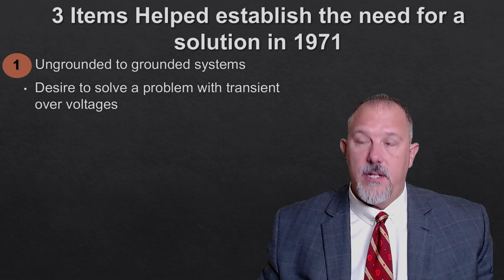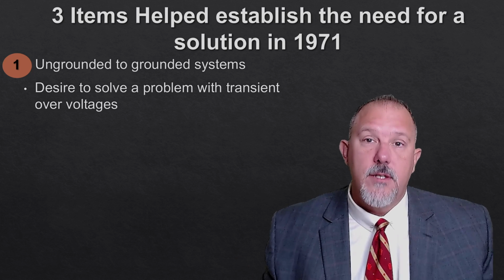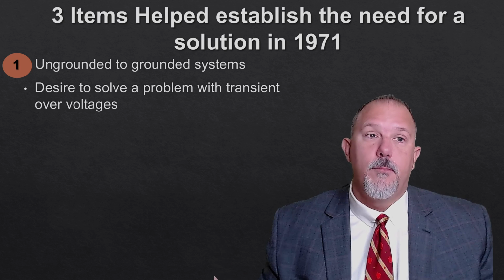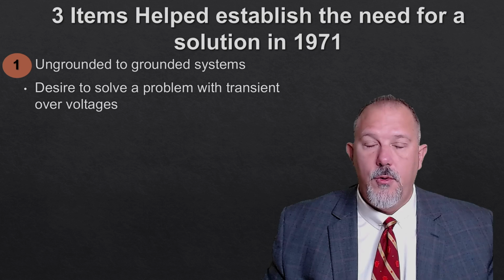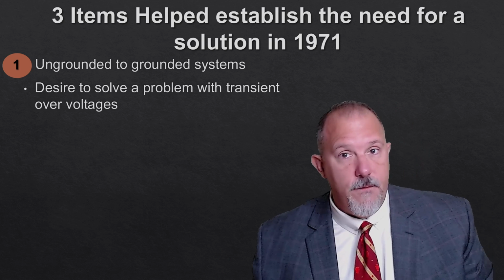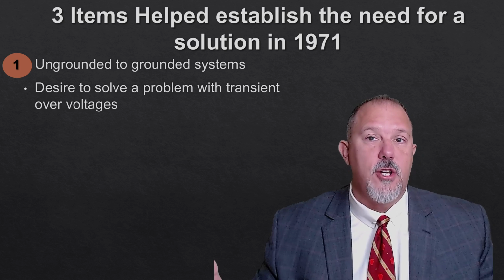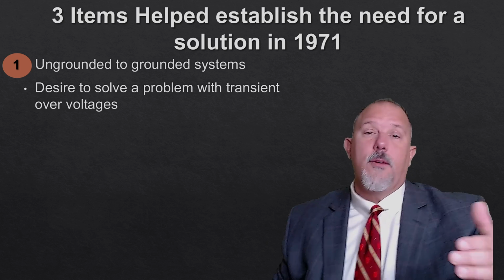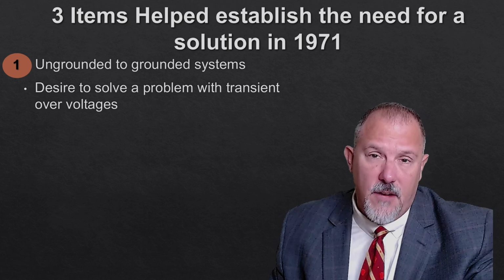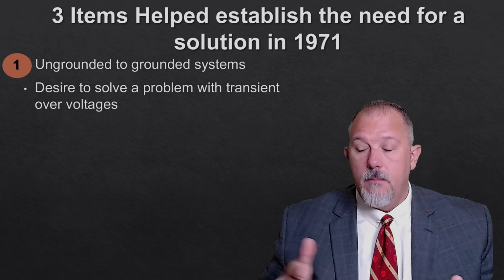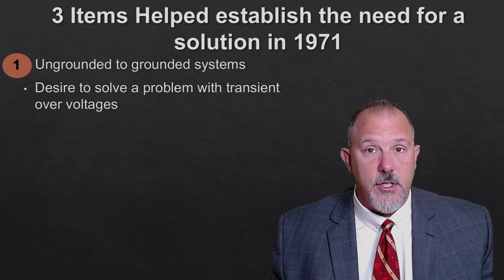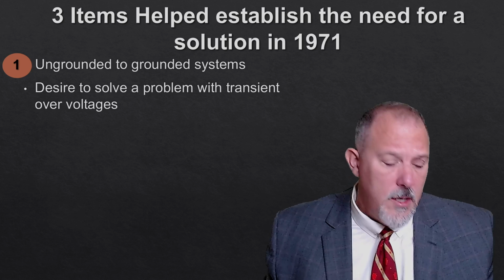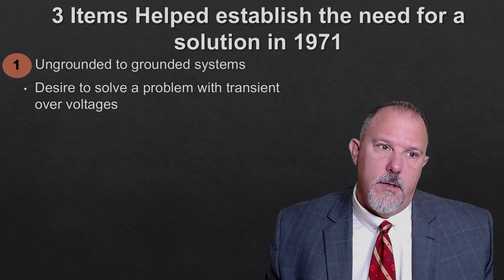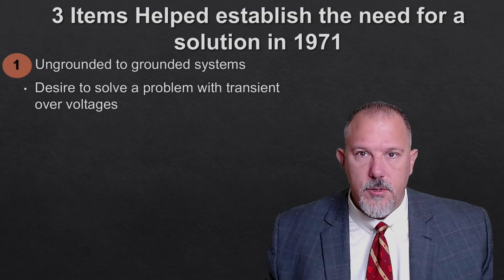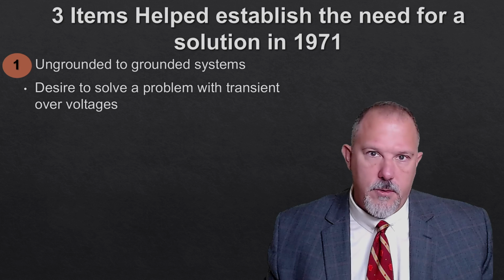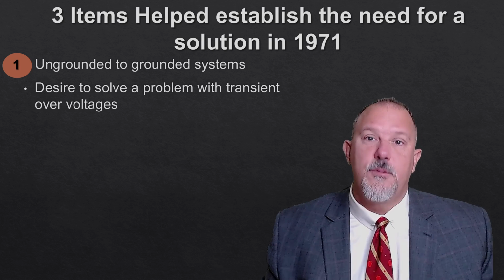Well, your system is subject to the system performance. When a fault occurs in a power system, you can have very high transient voltages. Different changes in the system can cause high transient voltages. And how does that exhibit itself in a power system? You'll see motor windings being damaged because of these transient voltages. And you think about an ungrounded system, it's not a residential home. Ungrounded systems are industrial facilities with a lot of motors and three-phase motors. And what they were experiencing were failures of motors.